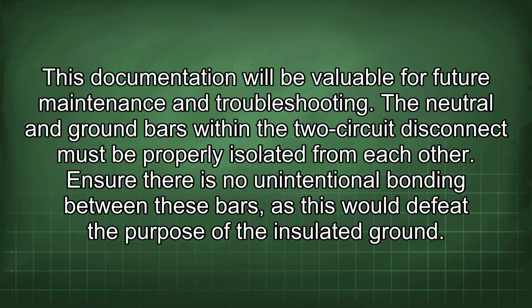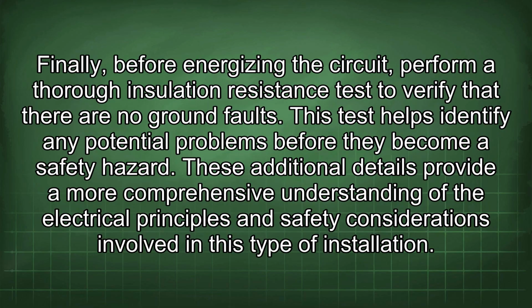The neutral and ground bars within the two-circuit disconnect must be properly isolated from each other. Ensure there is no unintentional bonding between these bars, as this would defeat the purpose of the insulated ground. Finally, before energizing the circuit, perform a thorough insulation resistance test to verify that there are no ground faults. This test helps identify any potential problems before they become a safety hazard.